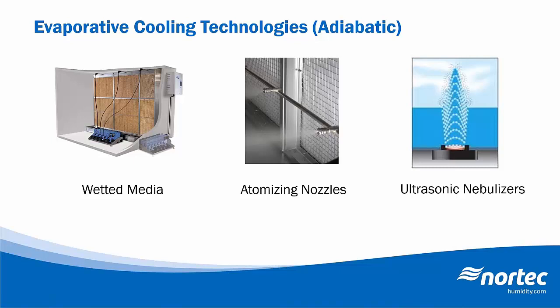Now, each of these systems has its own pros and cons, which we'll look at. Really, the technology should be selected based on the specific design requirements. One thing that I do want to point out is they all have one thing in common, and that is the need for hygienic operation. Both water quality and maintenance are extremely important whenever we're using an adiabatic system, and that's really to eliminate the risk of bacteria growth and Legionella. With that said, let's take a look at some of the more common ways that these systems can be applied. In these examples, we're showing a direct evaporative cooling system, but any of the three technologies that we mentioned here can be used.